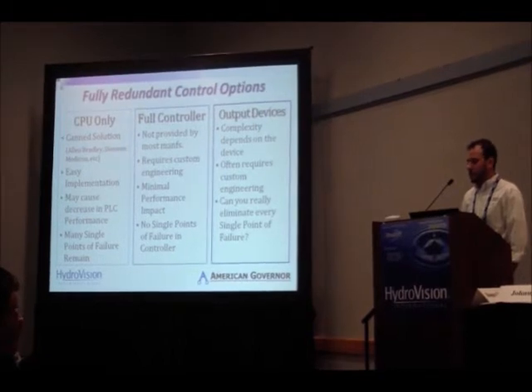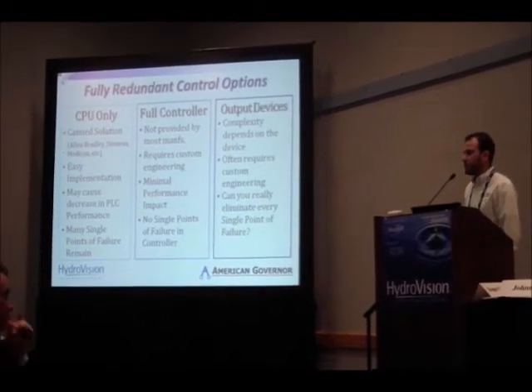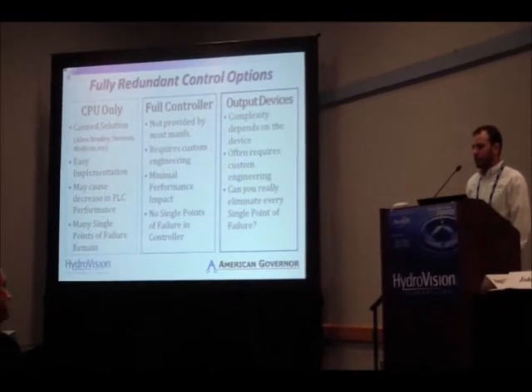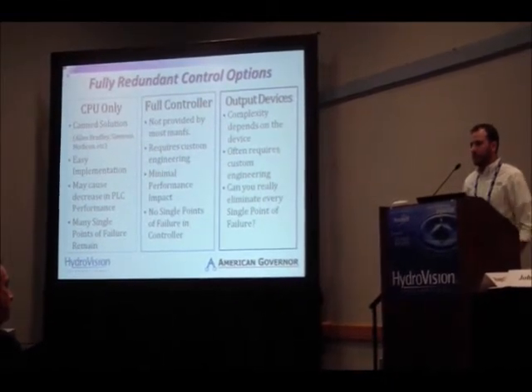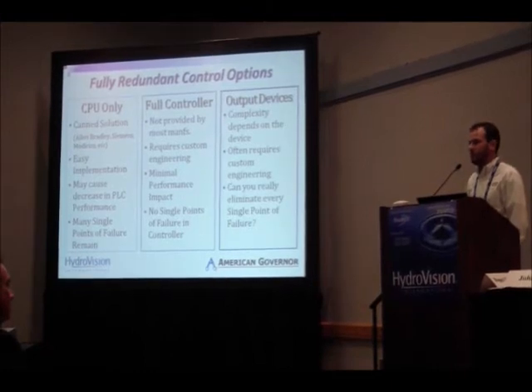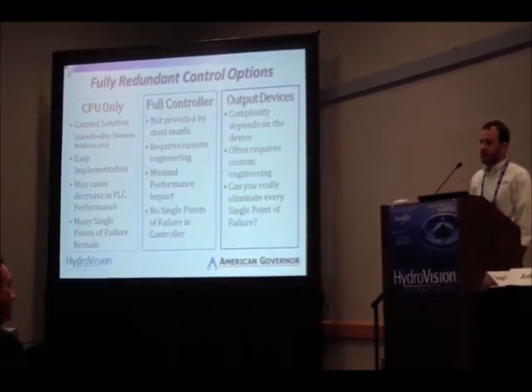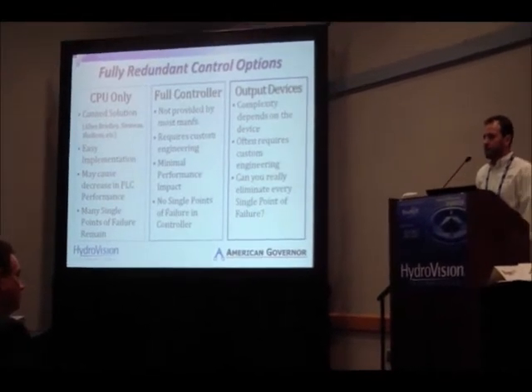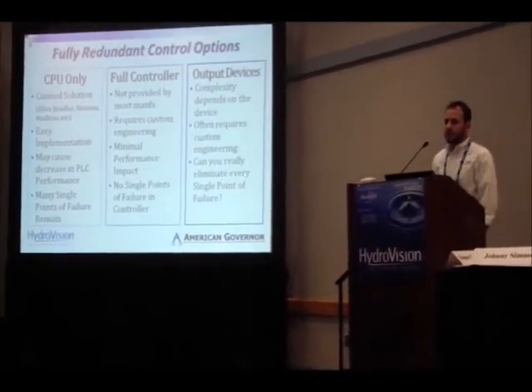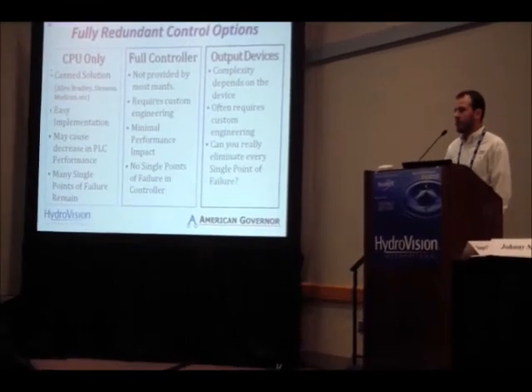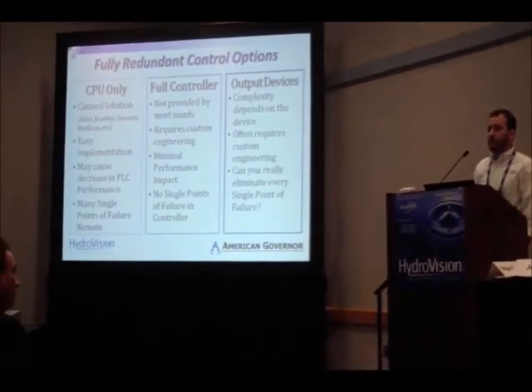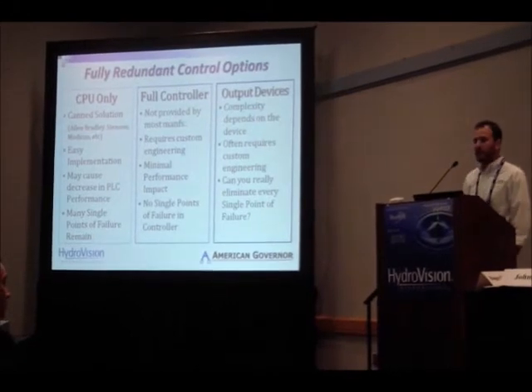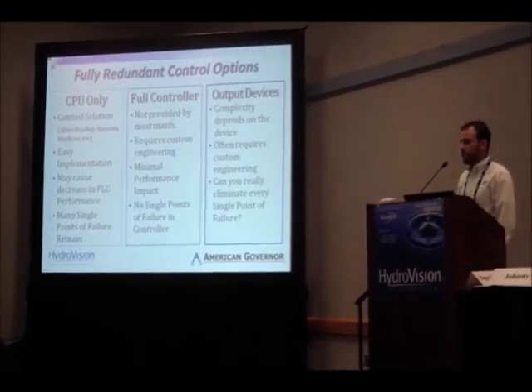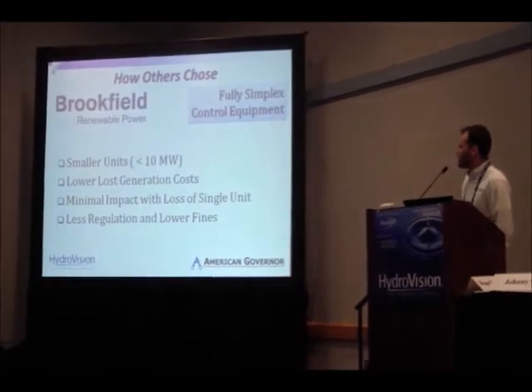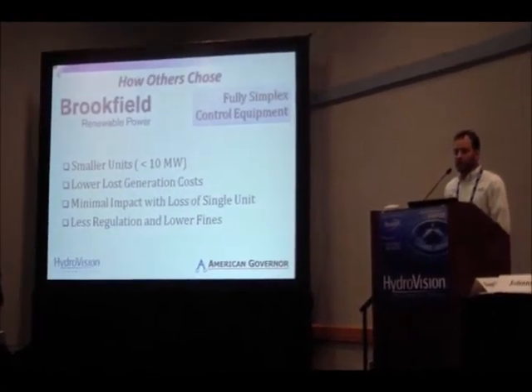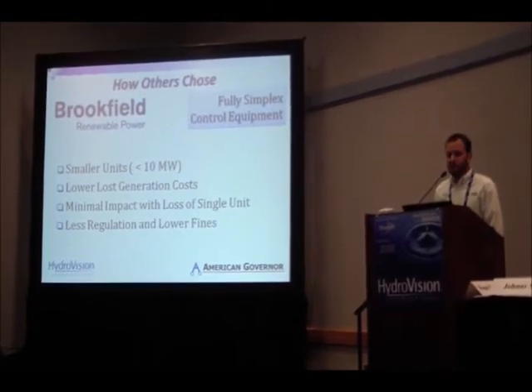So this is where, I'm not going to go into much more detail, but can you really eliminate every single point of failure? Are you trying to solve just a mantra of no single point of failure, or are you actually making serious improvements? And then also, what are your common modes of failure, where if you're talking about field devices, you're talking about devices that say dirty oil going to 2 valves, maybe having 2 valves isn't giving you that much bang for your buck anymore. Okay, so when would you want to use these types of systems? They're all valid configurations. So I'm going to choose a few utilities we've worked with and show you their situations that drove the decisions they made.